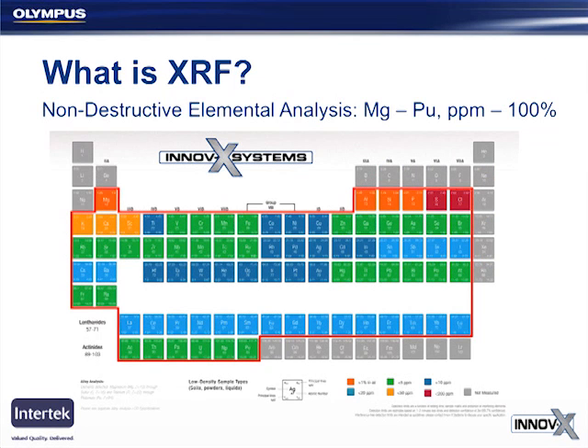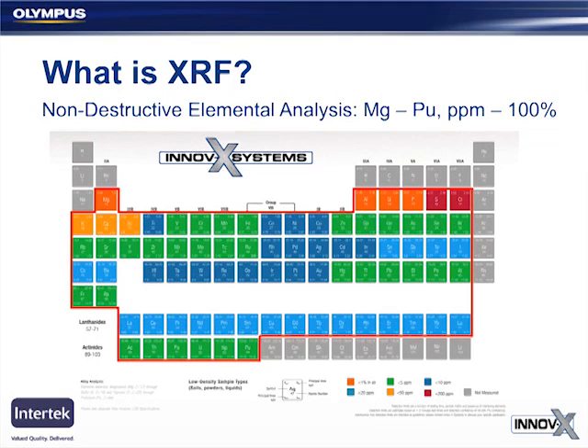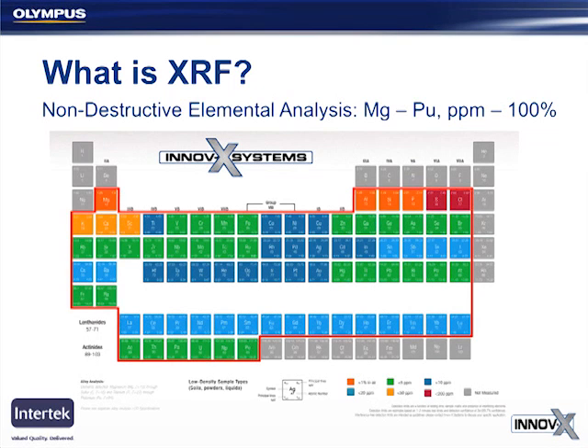So what this means is XRF is a pretty powerful and non-destructive technique to identify and measure the elements in almost any sample type. If we start with a periodic table of the elements like we have here, XRF can be used to measure any element that's highlighted here from ppm levels on up, starting with magnesium on up. This makes XRF useful in production testing, where regulations like RoHS are directed towards restricted elements: lead, cadmium, mercury, and other hazardous elements. XRF is well suited to detecting those elements in a variety of materials.